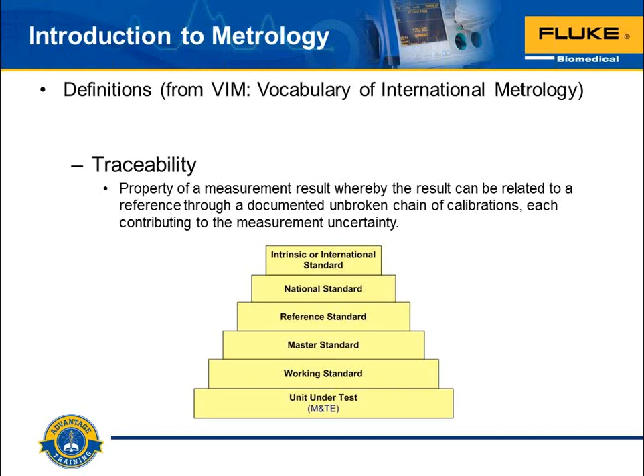So what that means is this. When you make that measurement of electrical leakage on a medical device, the measurement that you're making and the test instrument that you're making with needs to be traceable in an unbroken chain all the way back to the primary measurement of the ampere, all the way back. And you need to know what that traceability chain is for your test instruments. You really should know that, or someone in your department should know that. So we're bringing it up here because we think it matters. We think not all traceability is necessarily stacked up the same, and there's a lot of things that are happening in the field that may not give us exactly what we think we're getting. So this is about traceability. It includes the concept of uncertainty.